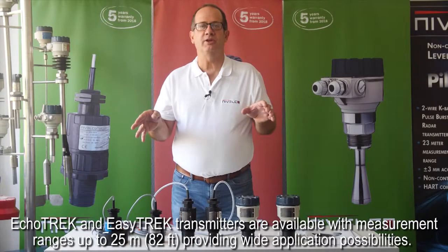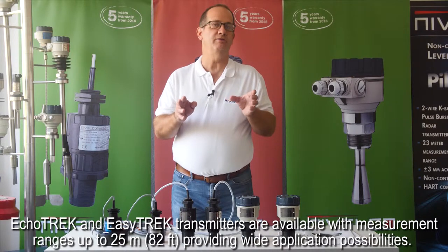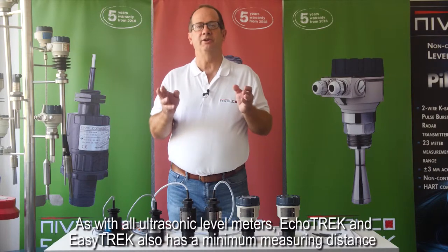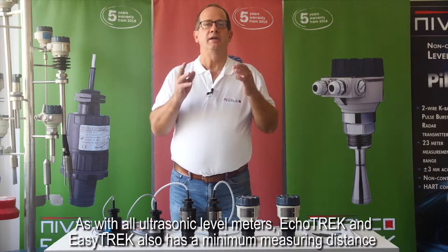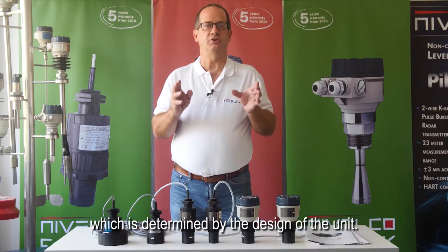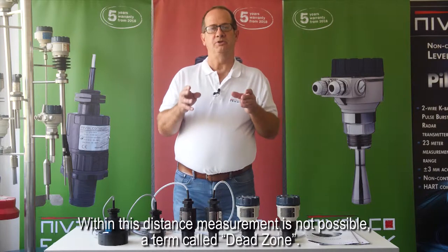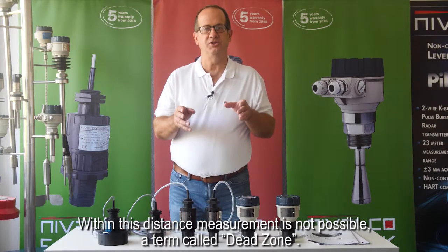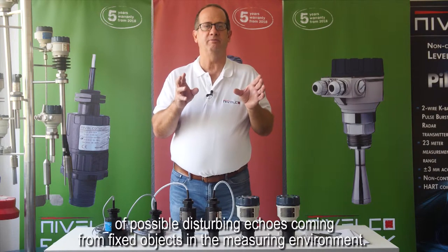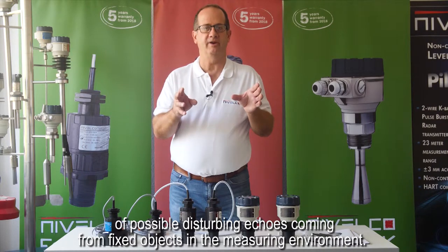ECHOTREK and EasyTREK transmitters are available with measurement ranges up to 25 meters or 82 feet, providing wide application possibilities. As with all ultrasonic level meters, ECHOTREK and EasyTREK also have a minimum measuring distance which is determined by the design of the unit. Within this distance, measurement is not possible — a term called dead zone. This distance can be extended by programming in order to avoid disturbing effects of possible echoes coming from fixed objects in the measuring environment.